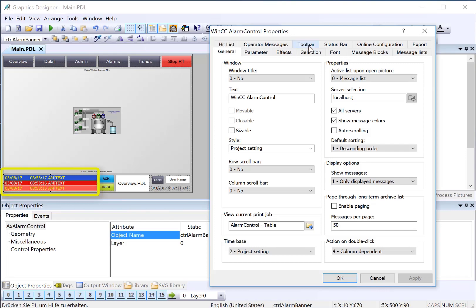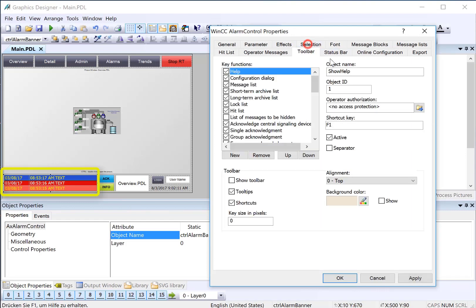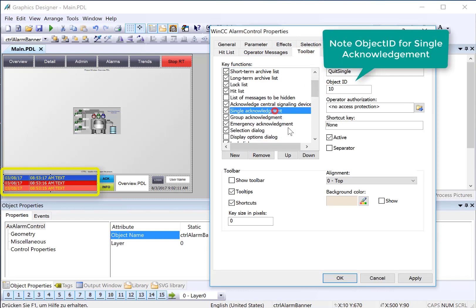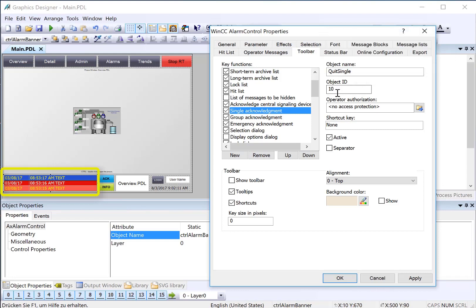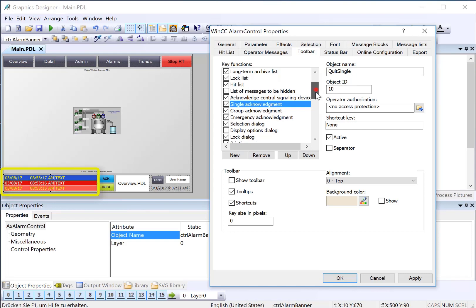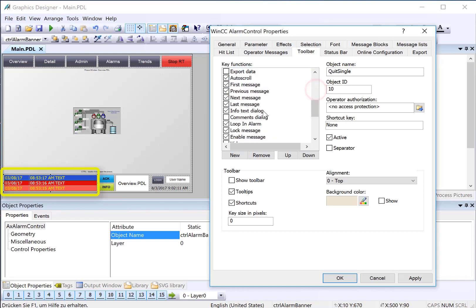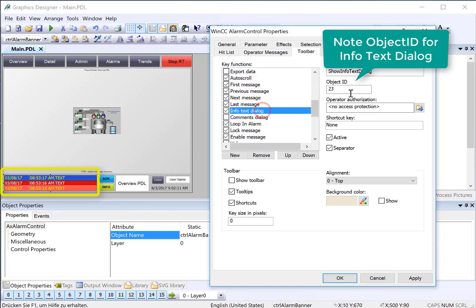The second piece of information is on the toolbar tab. We go find the button that we want to duplicate the functionality of and just note the object ID. We can use this to duplicate that functionality using a direct connect. So single acknowledgement is 10. And info text dialog is 23. So we can just hit OK here.